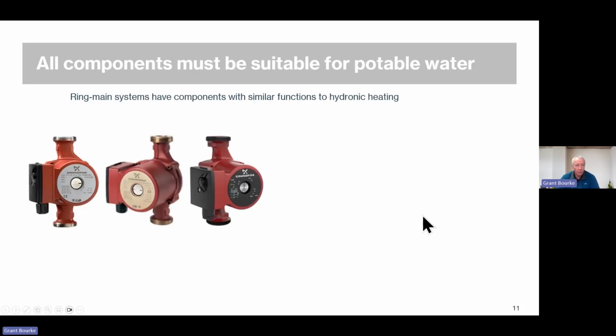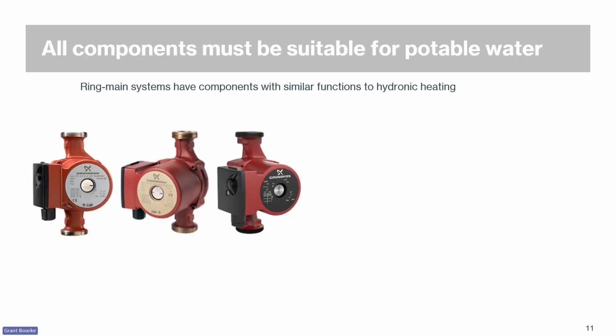So a common one that I see, if you look at these little Grundfos circulators from left to right, the one on the left is stainless steel, the one in the middle is bronze, and the one on the right is cast iron. I walk up to an awful lot of ring main installations and I see a little black escutcheon on the Grundfos pump indicating it's cast iron, and it really shouldn't be there. So just a word about that. Other Grundfos circulators that are bronze have black escutcheons on them, so it doesn't mean that all black markings are bad, but you need to make sure that you're using the right components for potable water.